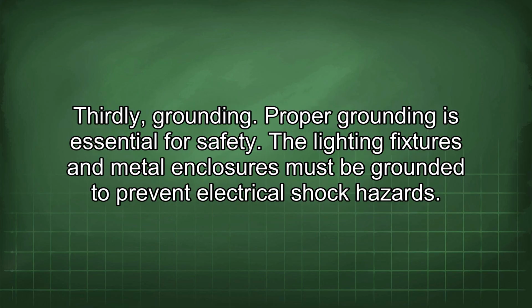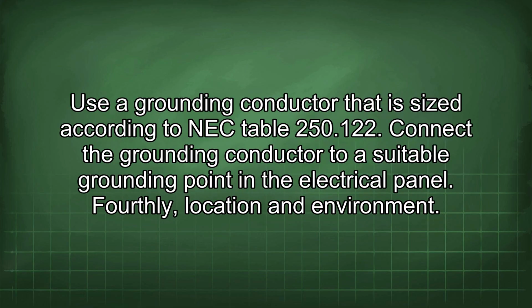Thirdly, grounding. Proper grounding is essential for safety. The lighting fixtures and metal enclosures must be grounded to prevent electrical shock hazards. Use a grounding conductor that is sized according to NEC Table 250.122. Connect the grounding conductor to a suitable grounding point in the electrical panel.